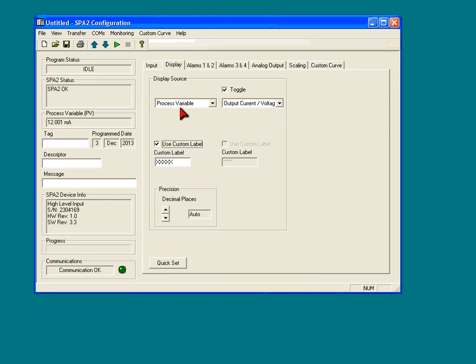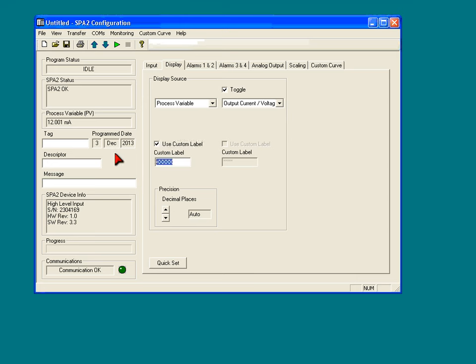The scaling feature - let's say if you had a 4 to 20 milliamp input, you would want to use a custom label if you wanted to display 0 to 100%. So you're scaling your 4 to 20 to 0 to 100, and then down in the custom label, you can put an abbreviation for percent if you'd like.